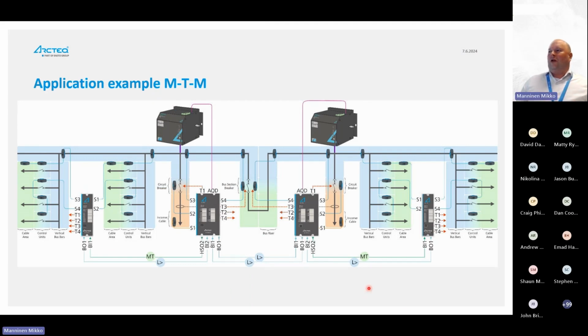This is an example of a low voltage panel, low voltage switchgear, low voltage MCC or similar. There are many ways to say it, depending on which part of the world you are in, but it is a low voltage board anyway. And the most typical low voltage board you can find is called main-tie-main. So one main breaker is here, then the tie breaker, and then another bus which is called main 2. And different relays measuring current, monitoring light. Same here, it's a subunit for this, only monitoring light. And then the arc quenching system bolted to the bus bar.